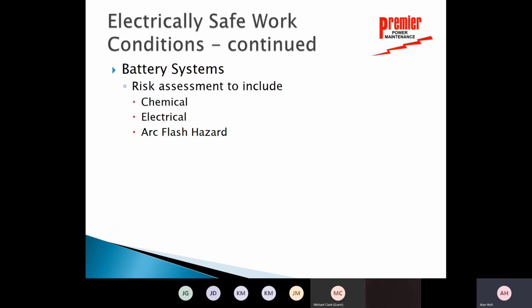We talk a little bit about some other aspects of electrical safety. Battery systems. If you have to work on a battery system at Marathon, part of your job hazard risk assessment procedure has to include not just our electrical hazard, not just our arc flash hazard, but we also have to identify the chemical hazard of working around batteries as well. I think we typically mention that, but basically, when we do job hazard assessment and job safety analysis, we talk a lot about the electrical safety, which we must, but they want us to also really address the chemical safety and working around those batteries.